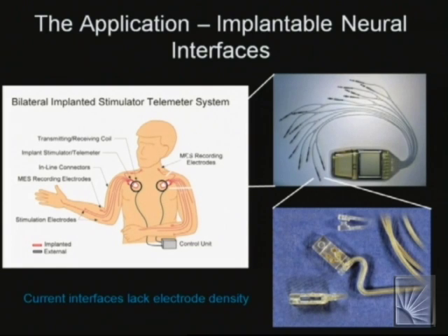And the platinum foil interface allows for more contacts per unit area than the platinum tip, with the idea that one would desire higher pixelation at a particular nerve site to get added functionality. Now, none of these structures are made using microfabrication techniques, and therein lies a limitation and an opportunity. The density of electrode arrays that one could produce in a structure like this is, of course, going to be limited by the manufacturing techniques used. And in this case, these foils are hand cut or machine cut, and the structures are hand assembled.